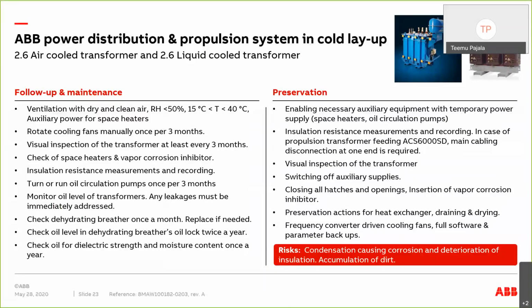And then especially important on the liquid cooled transformers is to check that there are no leakages happening. If there is, they need to be fixed. And then dehydrating breathers need to be checked, and oil filled in the cup underneath. And then of course if the breather is getting old, then replace as needed. And then for condition monitoring of the liquid cooled transformer, oil sampling should continue at the once per year frequency, like it was in the operation.